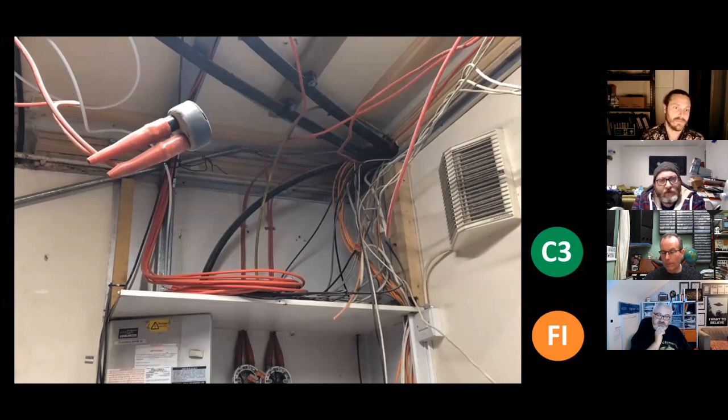This is the trouble during these sorts of projects. Is that conduit to the left, has that fallen down, or has some partition or wood been taken? That has been removed for a partition. Right, so that's just dropped for now. Yep. Okay. Yeah, general builders, labourers. This is the hazard for construction. This is why construction is notoriously bad, is when you allow unskilled labourers, and I don't mean that in detriment, I mean just electrically unskilled labourers, near building services that are still running, they will tend to get crowbars and pop stuff off the walls and do their bit and hopefully put it back.